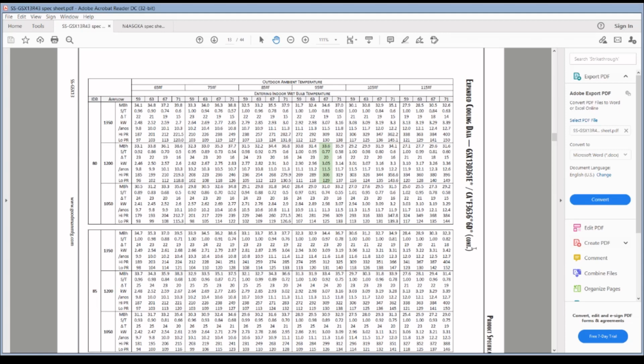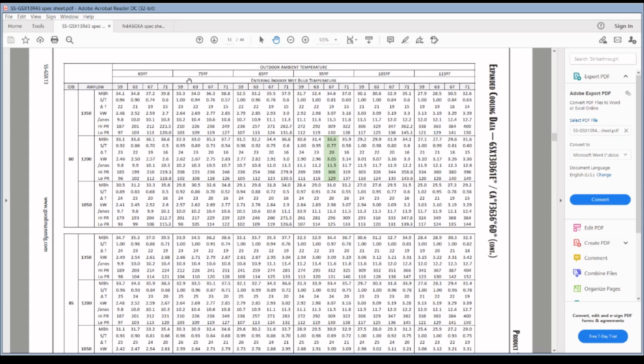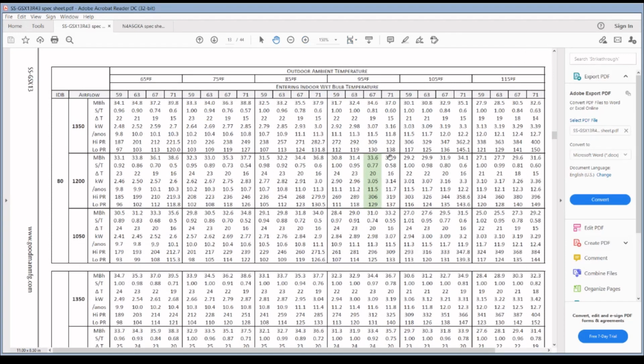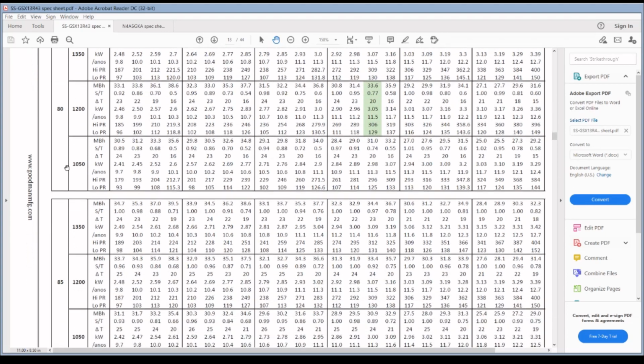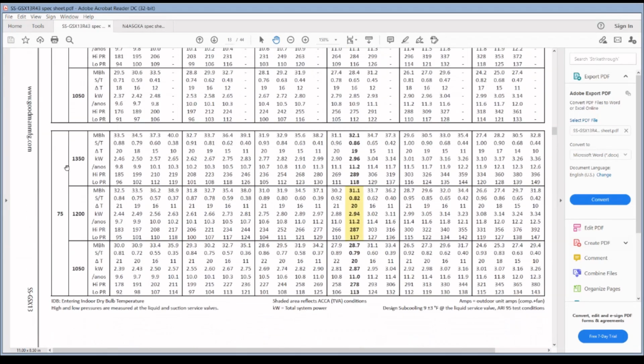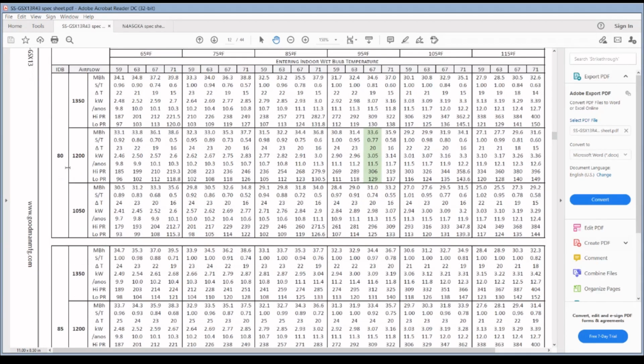And here we go. Now, you notice there are a bunch of different things. I'm not going to get into all of these. What I really want to focus on is sensible heat ratio. And we're going to drill in here on this chart, if I can expand this a little bit. Over on the left-hand side, we see a column that says IDB. And there are various IDBs. There's 80, there's 85, and if we go further, there's 75, there is 70 above that. So it gives us an indoor dry bulb temperature range. This is an indoor dry bulb temperature of 80 degrees. This would be considered your return air temperature.